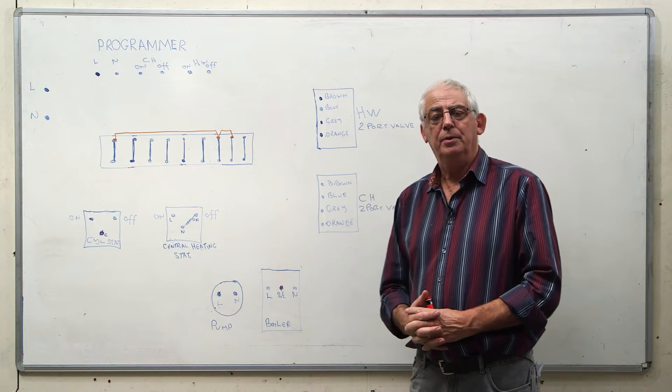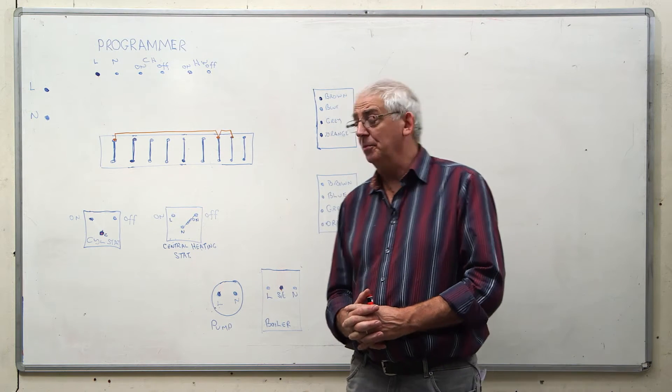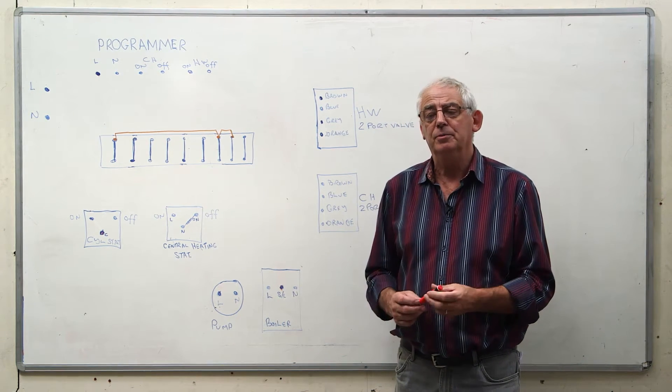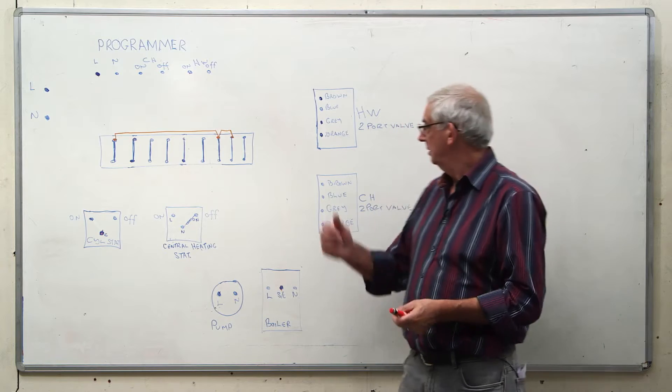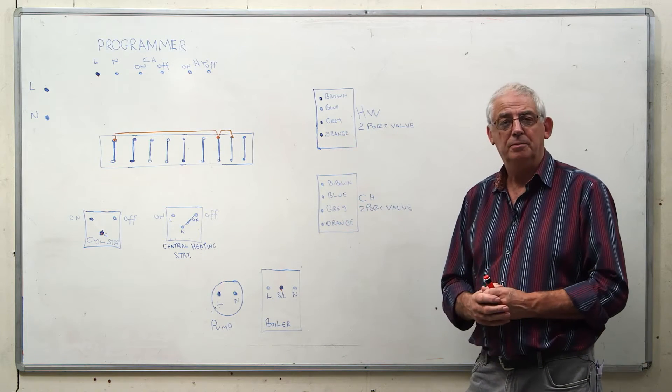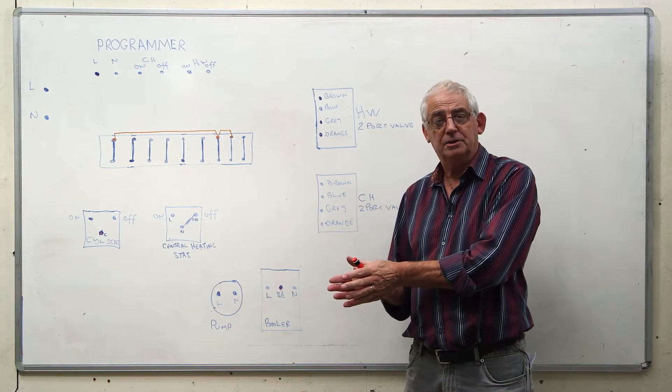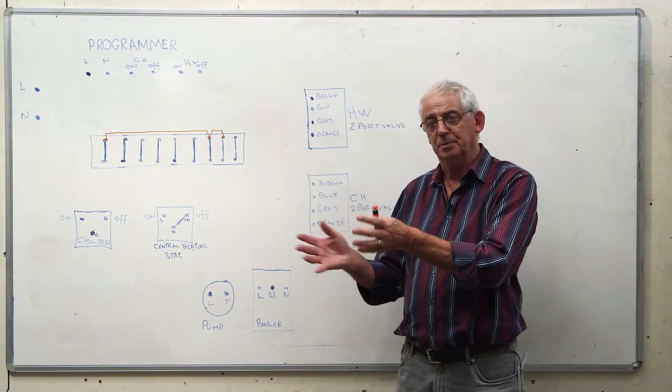I'm going to describe how to wire up a central heating system. The one we're looking at today is an S-Plan. An S-Plan would consist of two two-port valves, both of them are spring loaded so that when they've got current to them they'll open and when the current disappears they'll close.